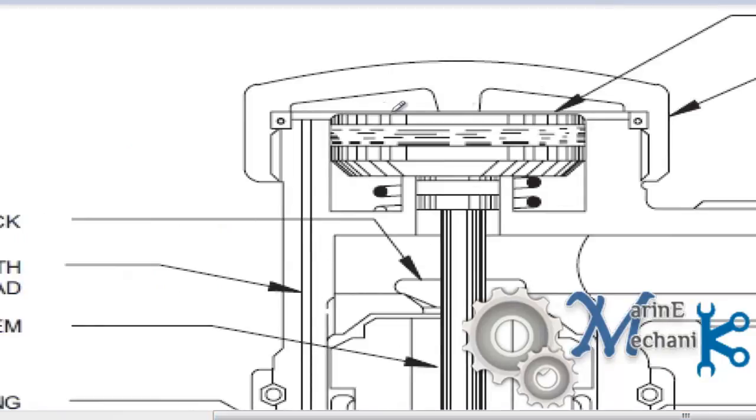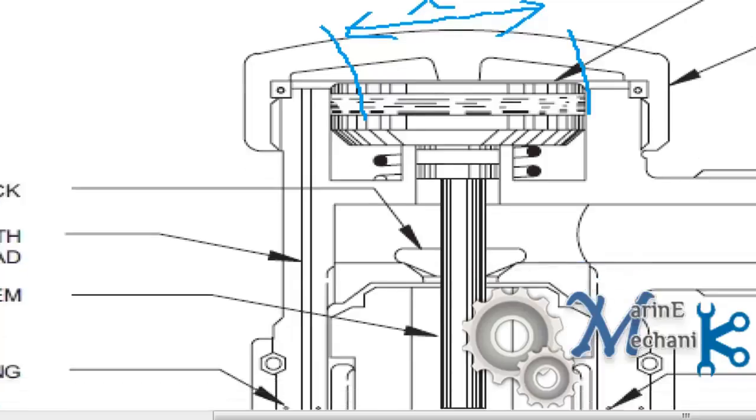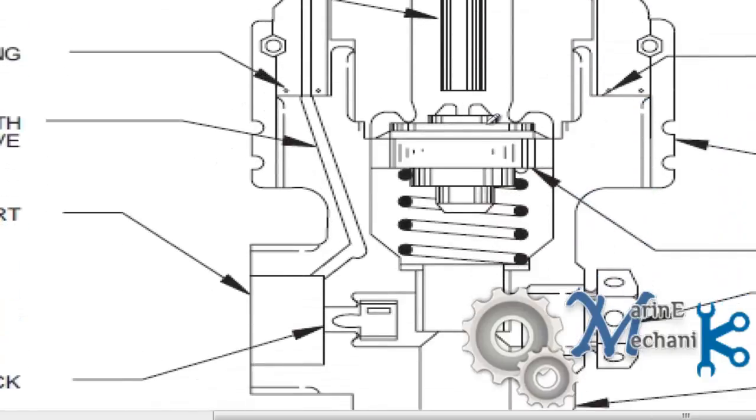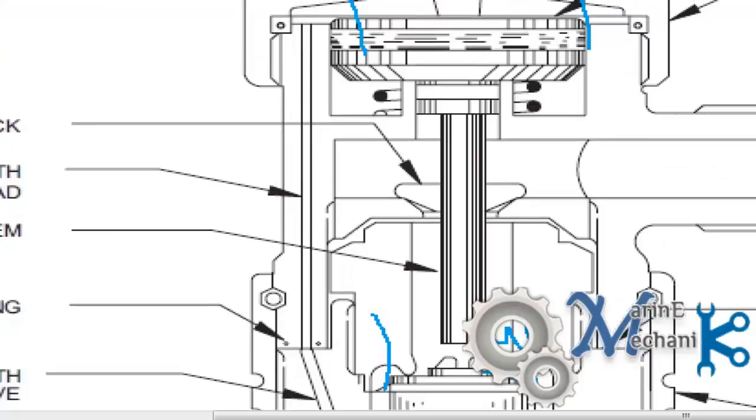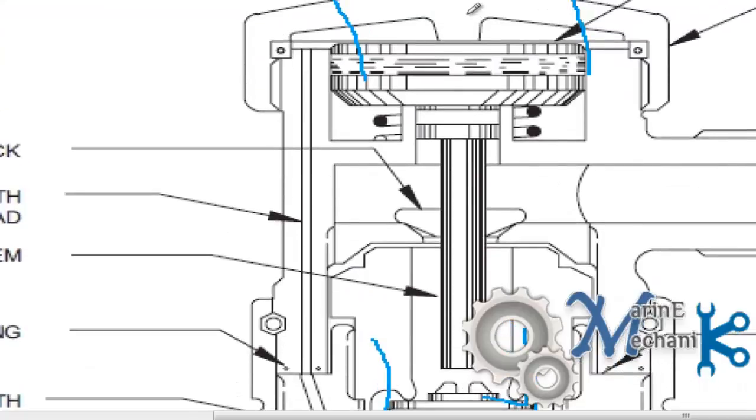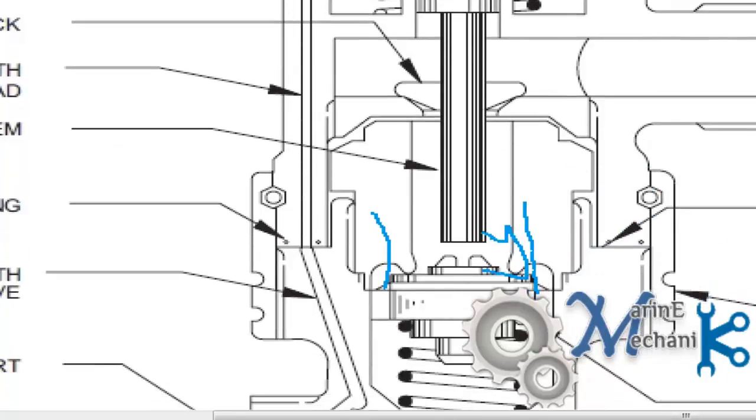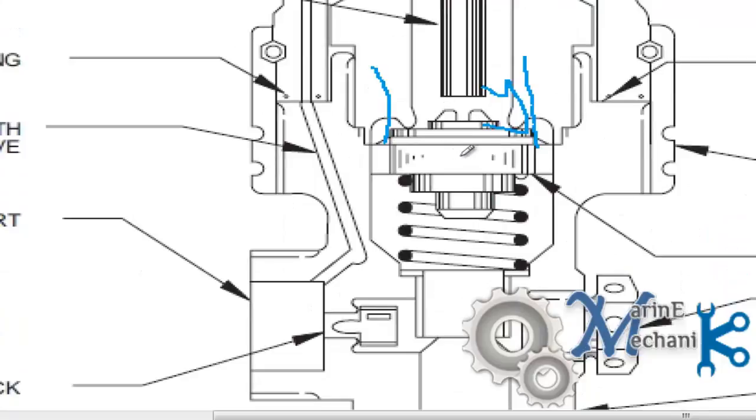When you see the area of this piston, let's say this is X. This piston area is more when compared with this. So as the area is more with the hydraulic basics, lesser pressure or smaller pressure is sufficient to push it down since the area is more. And as it is pushed down, the stem moves down and then opens this valve.